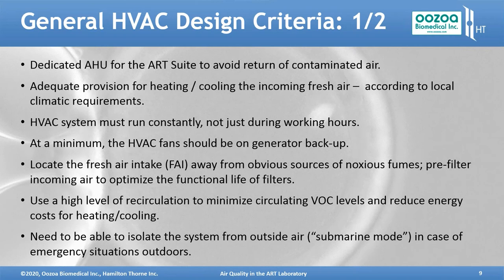The HVAC system needs to run constantly. You can't just run it during working hours. These systems don't function that way. At a minimum, the HVAC fans should be on generator backup as well, so it will stay running even if you have a power failure.